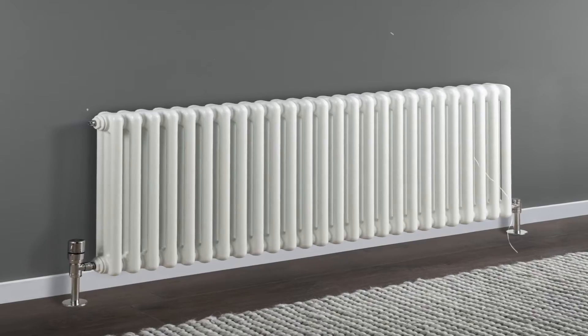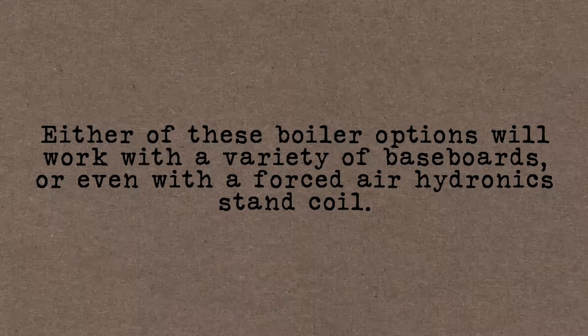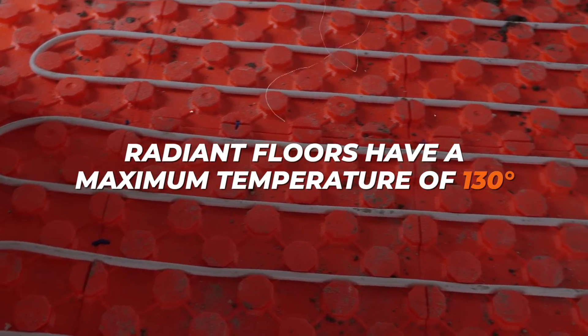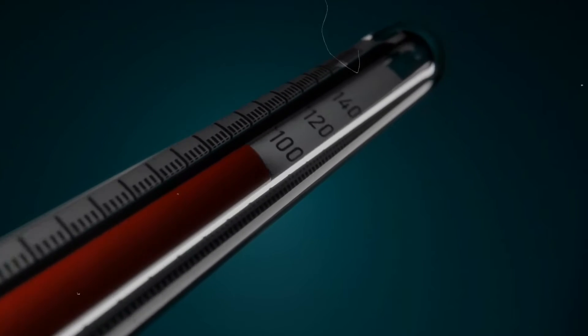Let's talk about the types of radiators and baseboards in your home, or perhaps you have radiant heated floors. Either boiler option will work with a variety of baseboards or even a forced air hydronic coil — you just adjust the set point temperature and how the system is piped. Radiant floors have a maximum temperature of 130 degrees, so with a properly piped secondary loop and a mixing valve, you can ensure the floor temperature stays within range. Baseboards typically run at 180 degrees.